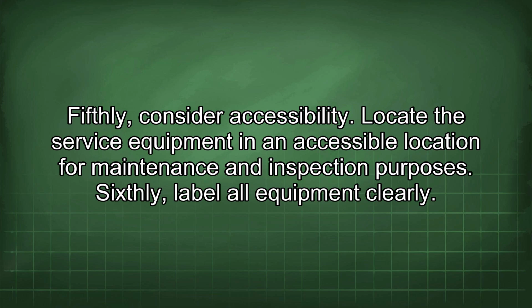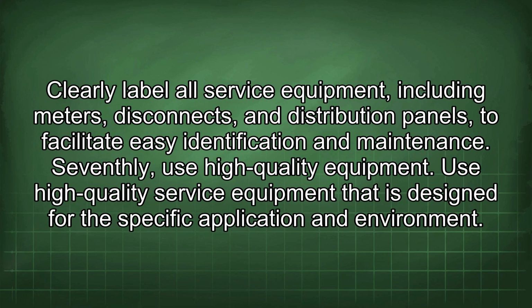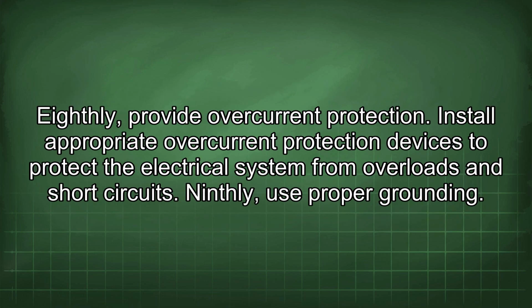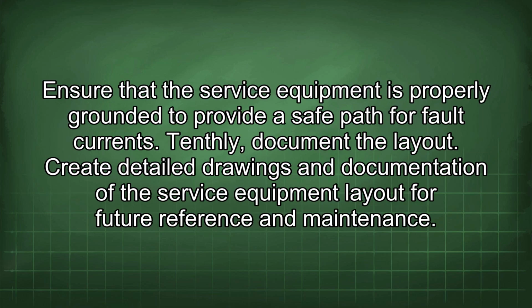Sixthly, label all equipment clearly. Clearly label all service equipment, including meters, disconnects, and distribution panels to facilitate easy identification and maintenance. Seventhly, use high-quality equipment. Use high-quality service equipment that is designed for the specific application and environment. Eighthly, provide overcurrent protection. Install appropriate overcurrent protection devices to protect the electrical system from overloads and short circuits. Ninthly, use proper grounding. Ensure that the service equipment is properly grounded to provide a safe path for fault currents. Tenthly, document the layout. Create detailed drawings and documentation of the service equipment layout for future reference and maintenance.